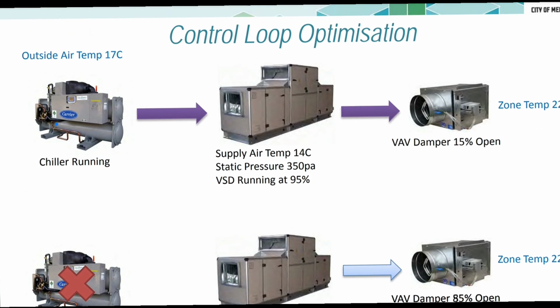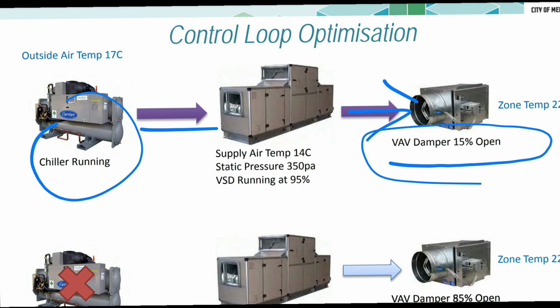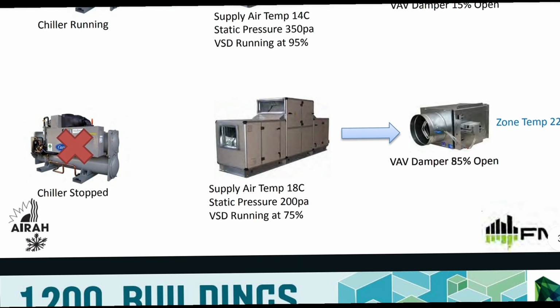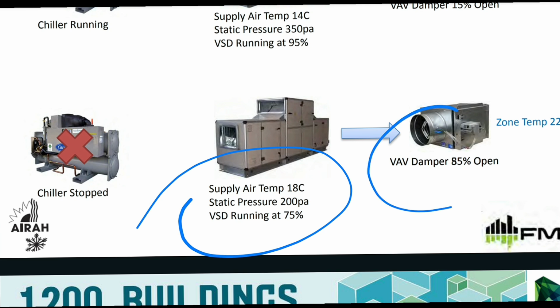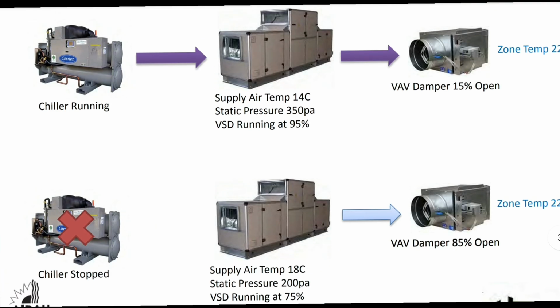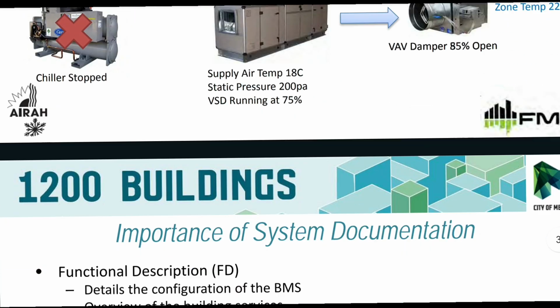Like, chiller running: supply air temperature 14 degrees Celsius, static pressure 350 Pa, and VSD running at 95%, VAV damper is 15% open. Next, chiller stops: supply air temperature 18 degrees, static pressure 200 Pa, VSD running at 75%, VAV damper 85%. Okay, this is a comfort zone and this is also a comfort zone.